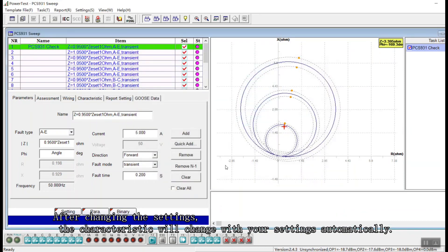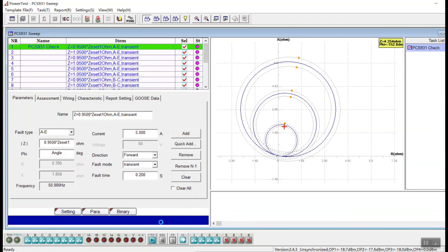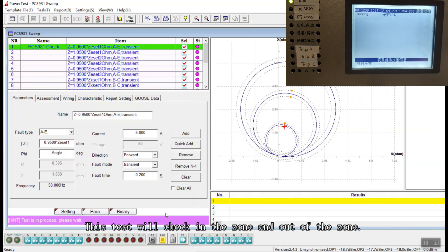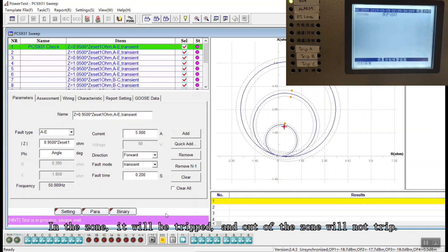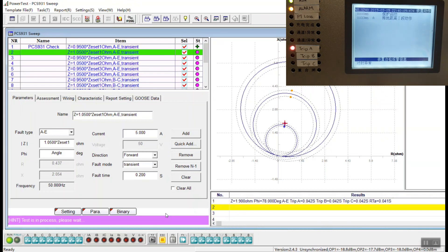After changing the settings, the test points will be changed automatically. Then just click run and the test will start running. In this test we will test the inner zone and out-of-zone. The inner zone will trip, and the next step will check the out-of-zone. It will check all the zones.